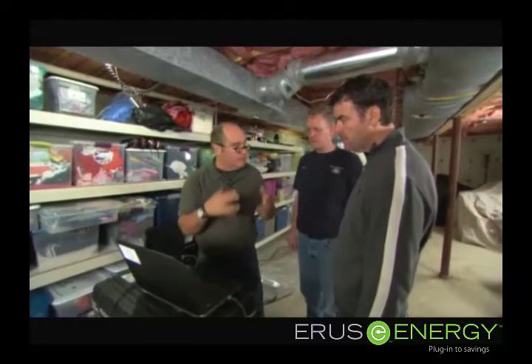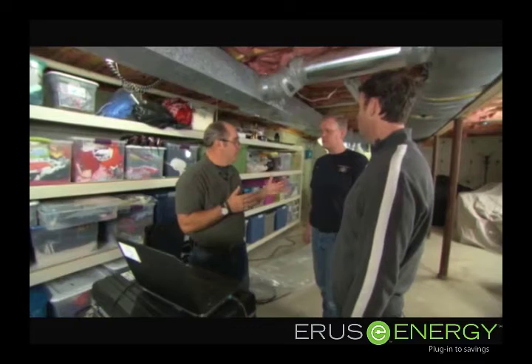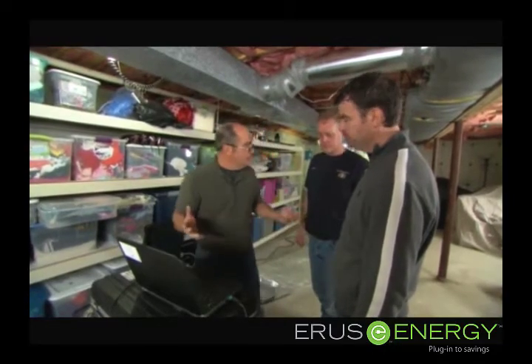So let's do the math. 307 CFM, this is a 4-ton system. That's just under 20%, right? Correct. Okay. So 20% is not coming back to be reheated. You're heating your neighbor's house. It's unbelievable. All right, so how do you seal the ducts?